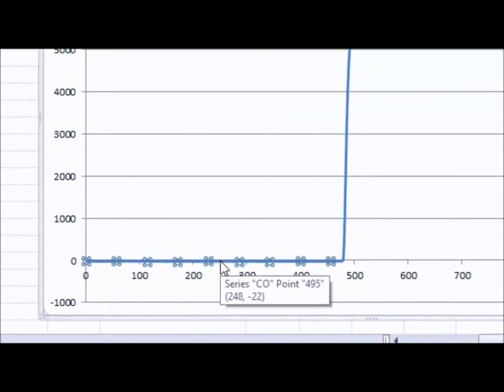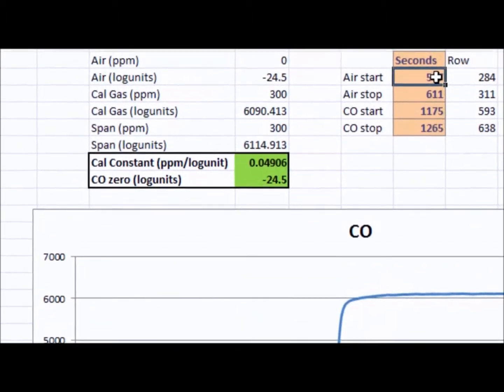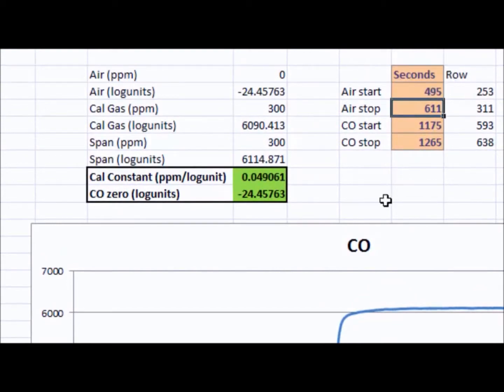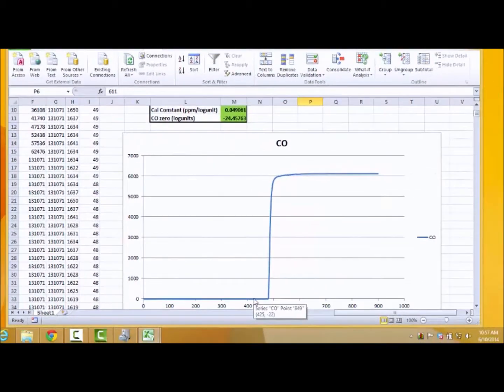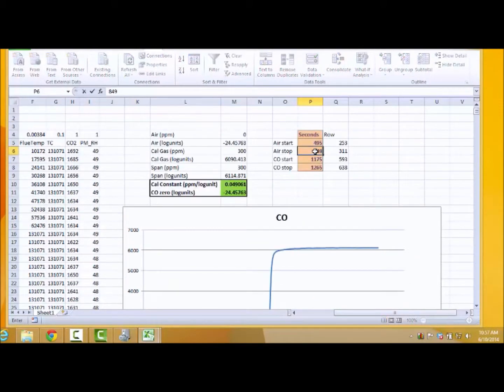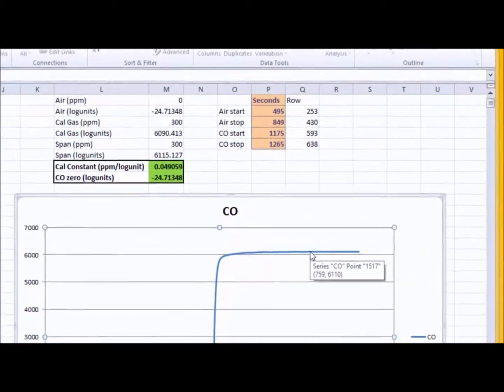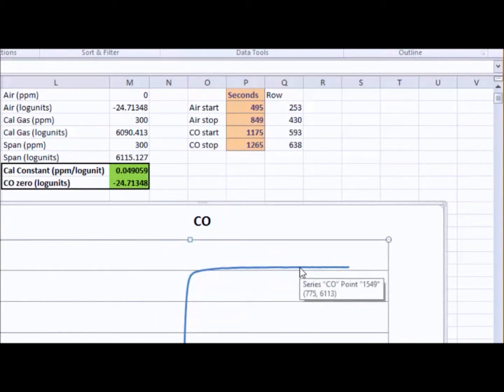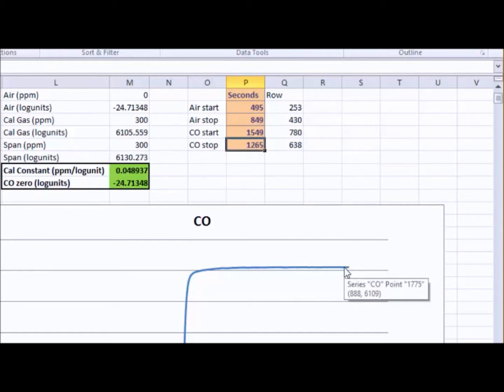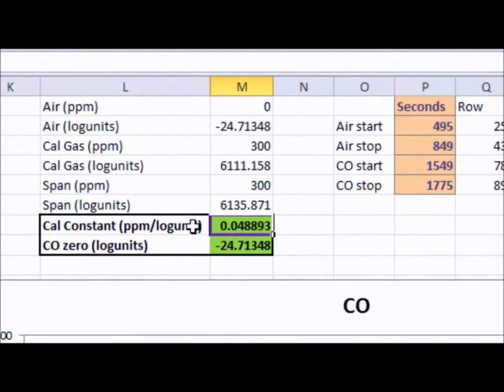In this case, we have 495, so let's enter that into the first box. That's when we'll start the average range. Here's a point we can use to end the average of the baseline, 849. So at 849 seconds, we'll enter the end of our averaging value. Next, let's find an average of the 300 parts per million section. Make sure the graph is leveled off and pick a value. 1549 looks good. Then find an end value. 1775 looks good. At this point, your calibration values will be displayed. The calibration constant in ppm per log unit will be entered directly into the sensor box. The CO zero value will be used to adjust the value already stored in the sensor box.